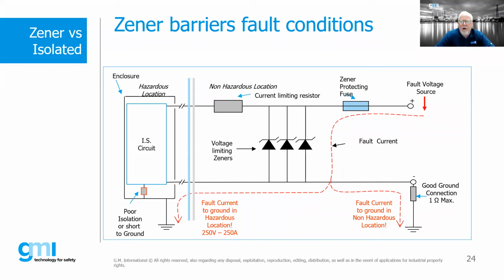And a lot of people have gone away from the Zener diode type products to go more towards isolator type products. If you think about it as an example, in many cases, if you're building a skid package and you're using Zener diode barriers, you have to have some sort of dedicated IS earth. And how do we know, if we're going to send that skid package out to a client in the middle of nowhere, that they've got a good, clean, dedicated earth? We can put all the warning labels and everything else, but if they don't tie it into a good, clean, dedicated earth, that's a big issue.